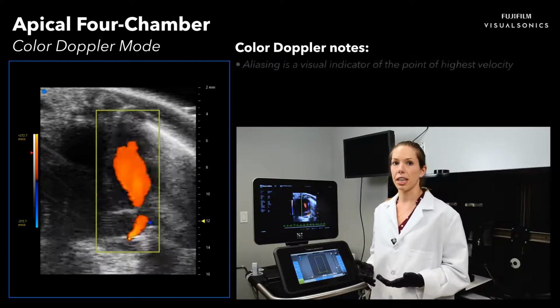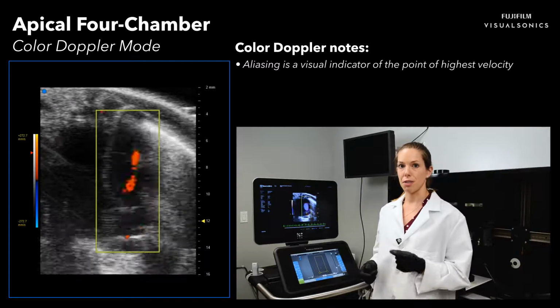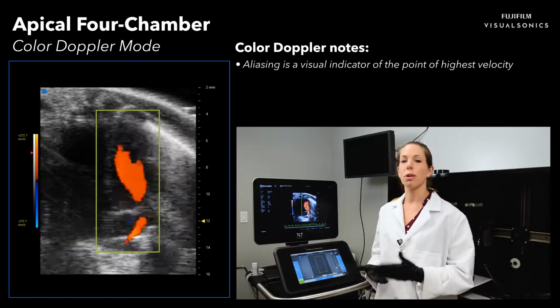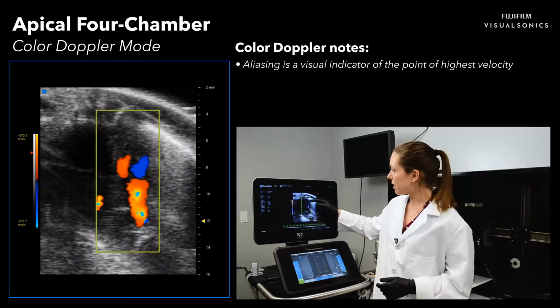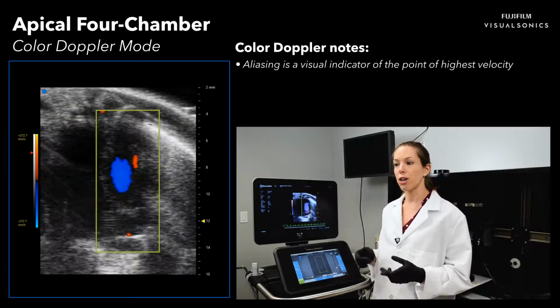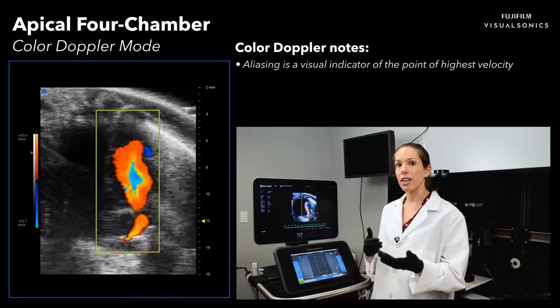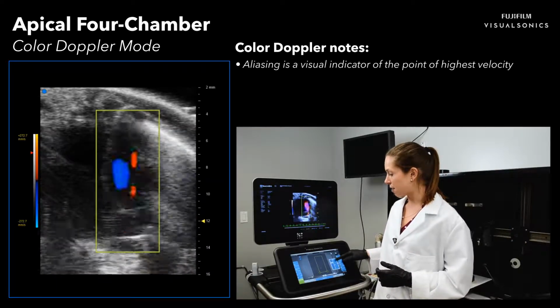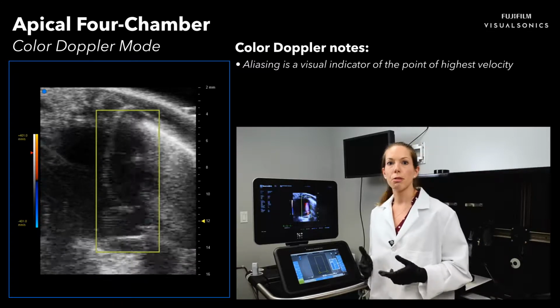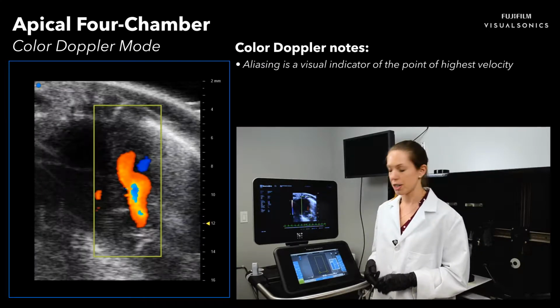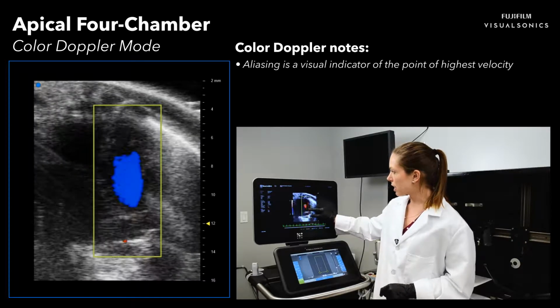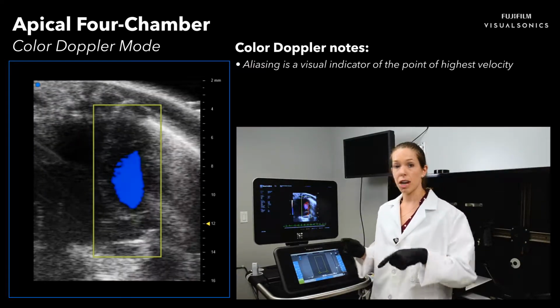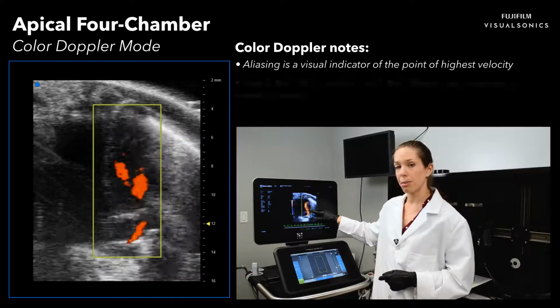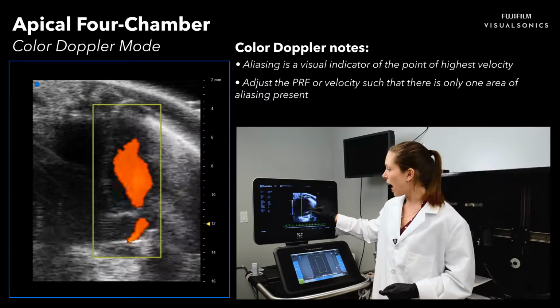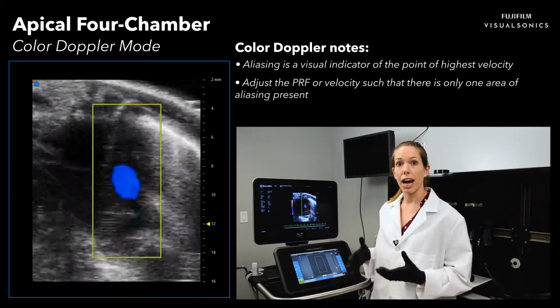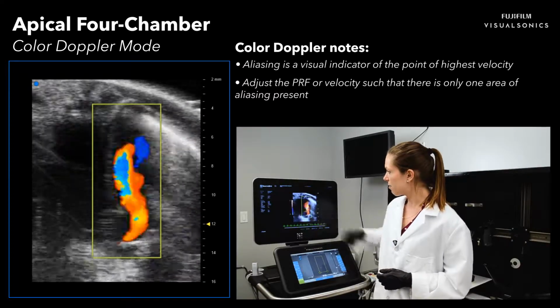Aliasing can be a good thing in Doppler imaging because it tells us where the highest flow is. And when we sample velocity, we only want to sample where that highest flow is. But if it wraps around too many times, then it's very hard to know where it's really high and where it is slow. So there is an optimal setting for adjusting the velocity, but it's going to be dependent on the pathology and the species that you're using. In this case, I really only want to see one area where it's wrapping around. I don't want it to wrap around everywhere. So I just move the PRF or the velocity to a point in which I only see one very smooth area of high velocity flow, like this.